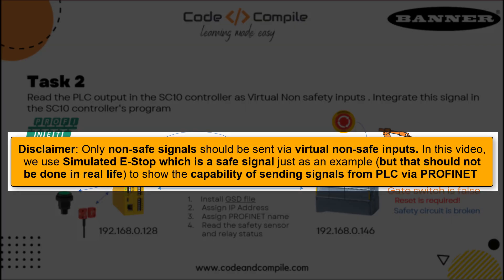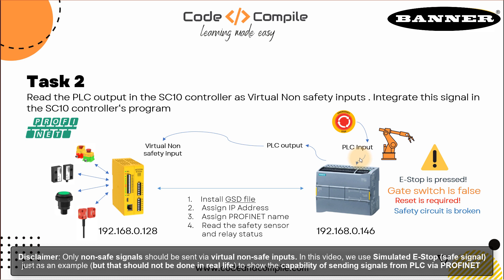Let's consider a situation when your PLC controller has an application with some e-stop buttons, and this is a different circuit compared to your circuitry of the SC10 controller. Let's imagine you cannot connect the e-stop directly to the SC10 controller, but you have to send it via PROFINET. It could be any situation — any gate switch, not only e-stop — but in this example we consider e-stop as a signal going via PROFINET to the SC10 controller. So we have to configure the program inside the controller, write a small algorithm in the PLC, and connect it all together. Let's do it step by step.